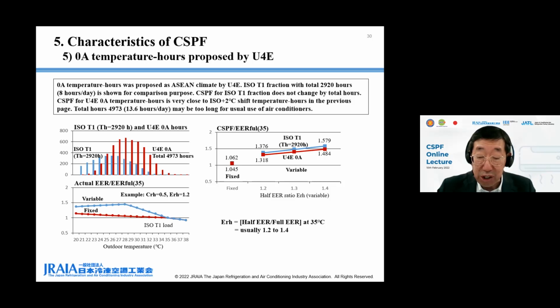Half capacity ratio CRH and half ER ratio ERH for the example variable capacity unit are 0.5 and 1.2. The right figure shows CSPF divided by 35 degrees C full ER for ISO T1 fractions and U4E 0A temperature hours for fixed capacity unit and variable capacity unit in usual range of half ER ratio ERH from 1.2 to 1.4.